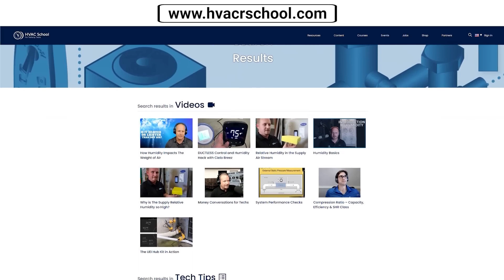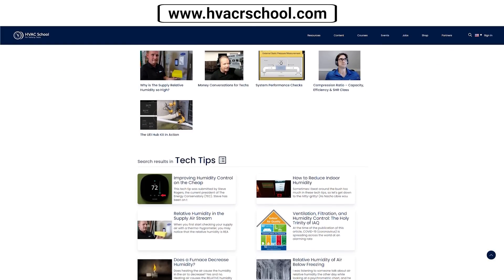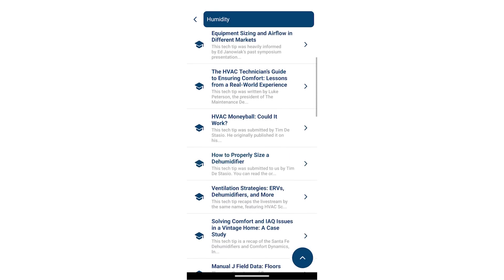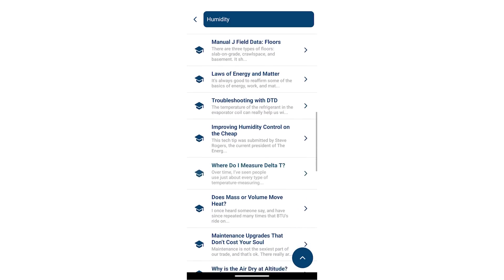You can look at surface temperatures, but things in the attic where insulation can help — that makes sense. But if the issue is underneath, do we really want to increase the surface temperature of that vent? Not really, especially not by increasing the system airflow, which is going to result in a warmer evaporator coil and less dehumidification. We have a lot of great articles on this at HVAC School. Look up humidity on the HVAC School website or app to find more. Usually the best way to solve these problems is to provide a series of solutions rather than just looking for that one simple thing — just sealing around the vent, unless it's really got a lot of gaps and cracks, generally isn't going to solve the problem. Think about it bigger, provide bigger solutions — that way you're going to take care of it for your client the first time.